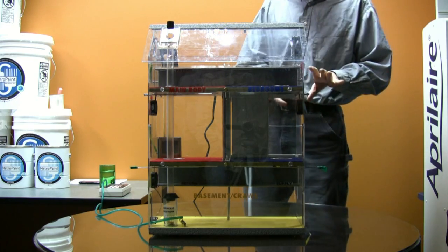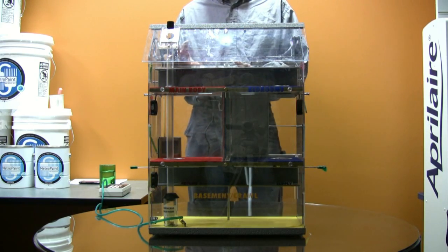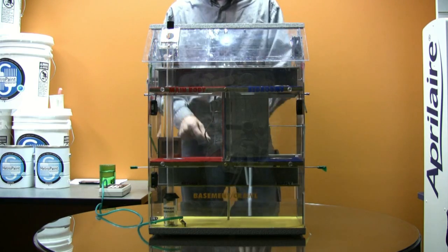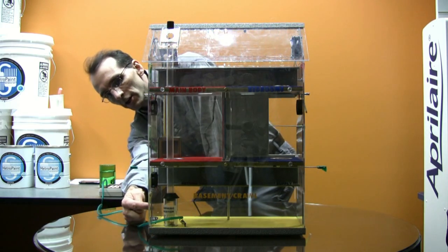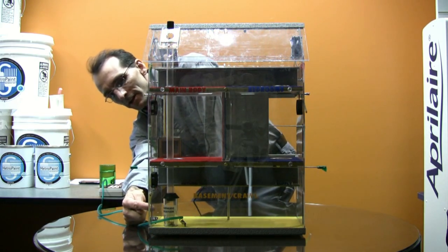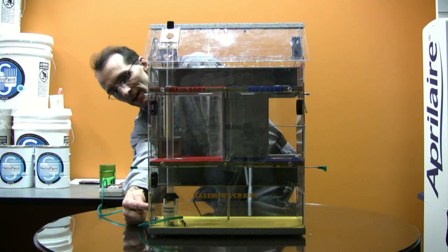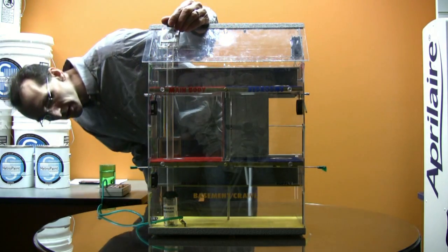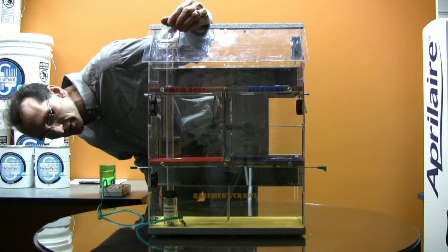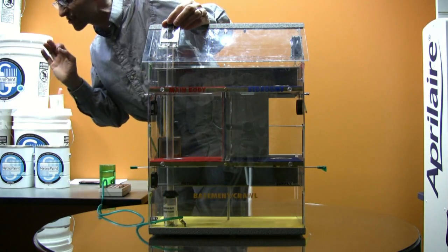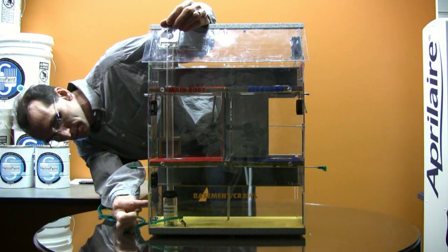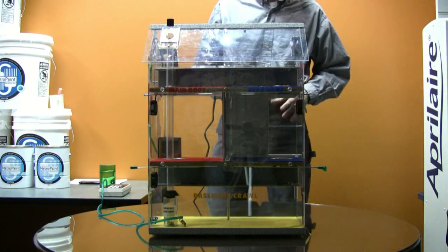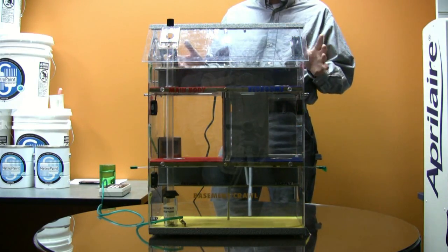So what we're going to do is test the conditions in a combustion safety zone of the house. Typically set up here, we have a naturally vented water heater tucked into the basement down here, which is a pretty standard situation. We've got a flue that comes all the way up and out of the house right here. It mimics a naturally vented water heater because there's a gap between the unit and the flue, and that's what you have on a standard atmospherically vented water heater.